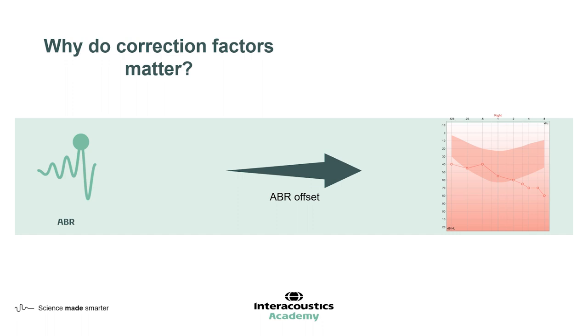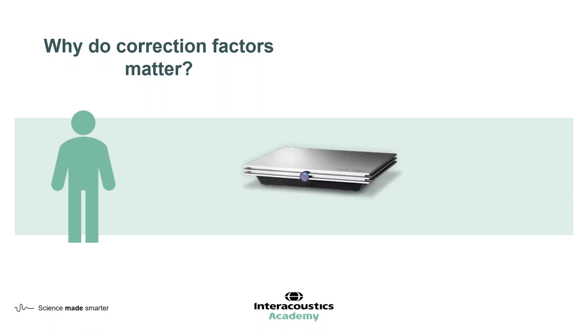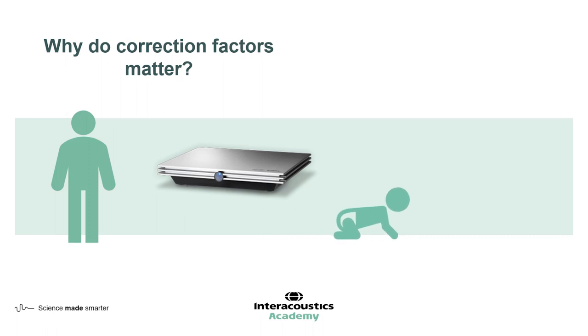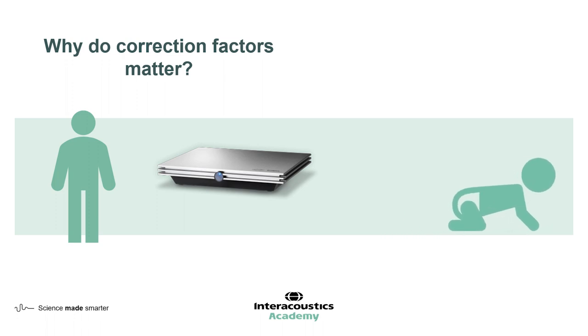This is called the ABR offset. Evoked potential systems are calibrated to adult data, but more often than not evoked potential testing, particularly the ABR, is used on babies. If we are testing babies, we need a way of converting the calibrated ABR stimulus into something that more closely relates to these infants. Our babies also grow very rapidly, and we'll talk more about how we need to account for that later.